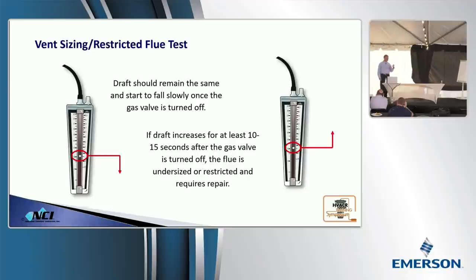Now, there's another symptom that makes it look like a combustion air problem. You guys mentioned this one earlier. What if the flue's restricted? There's a simple step you can add to this. Walk over to the gas shutoff on the equipment after it's running, kill the gas cock. Just turn it off and watch the draft.